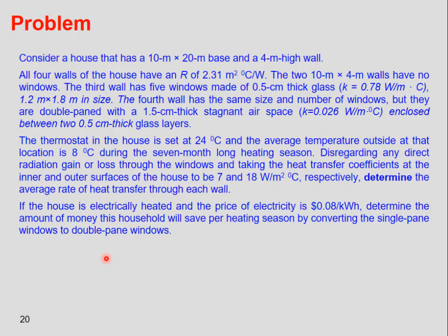In this example we are going to see how to use the thermal resistance concept to calculate the rate of heat transfer through the wall of a house. Consider a house that has a 10 meter by 20 meter base and 4 meter high walls. All four walls have an R or thermal resistance of 2.31 meter squared degree Celsius per watt. The two 10 meter by 4 meter walls have no windows. The third wall has five windows made of 0.5 centimeter glass with thermal conductivity of 0.78 watt per meter degree Celsius.